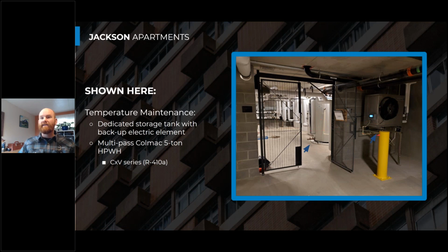And this is a 410A heat pump water heater too, so it's better suited for that multi-pass heating cycle, as well as it can operate at lower air temperatures. So there's some benefit there, or some reason why we could locate it outside.